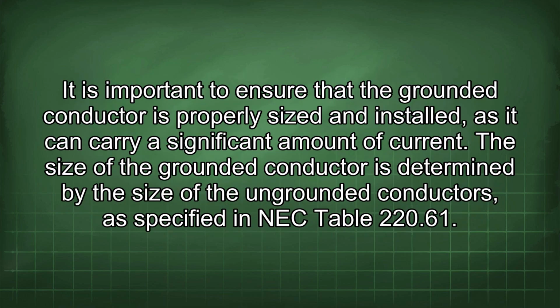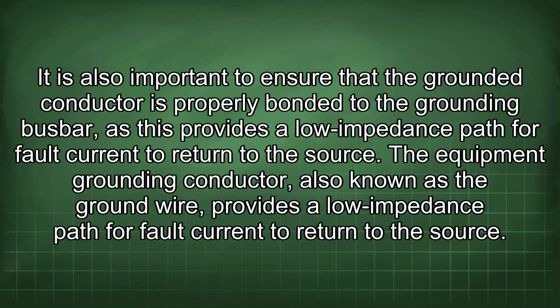It is important to ensure that the grounded conductor is properly sized and installed, as it can carry a significant amount of current. The size of the grounded conductor is determined by the size of the ungrounded conductors, as specified in NEC Table 220.61. It is also important to ensure that the grounded conductor is properly bonded to the grounding busbar, as this provides a low impedance path for fault current to return to the source.